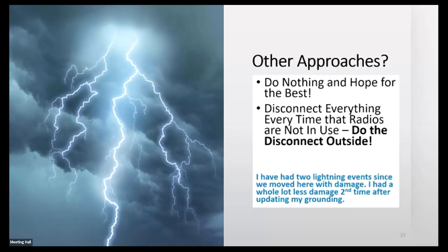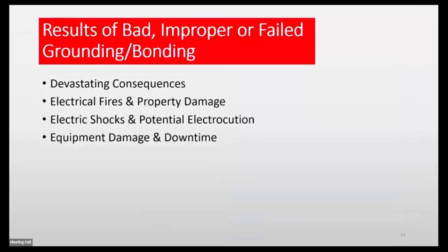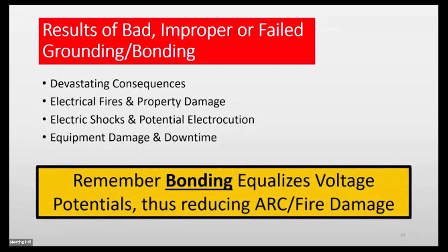Okay, I've had 2 lightning hits - one I was home for, one I wasn't. So what are the results? Bad and proper, devastating consequences - electrical fires and property damage. How does that happen? Remember I said equal potential? Grounds - you had 2 grounds that are not connected to each other. They don't raise and lower at the same time. Guess what happens? You have 2 voltages that are different from each other. There's arcing between them. Arcing - how do you start a fire? There you go, need I say more? Electric shocks, potential electrocution, damaged equipment, downtime. Bonding equalizes the voltage, reducing the arc fire damage.